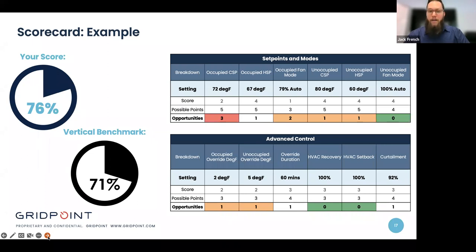So keep at it. And to give an idea of how these are scored, we looked at the definition of the scorecard in the previous slide. How this works is the setting across the columns shows us what we're looking at. For occupied cooling set point, we're looking at a setting of 72 degrees. That's what this customer's average occupied cooling set point was across their 24 units. So that gives them a score of 2 out of a possible 5 points, which gives their opportunity score 3 points.